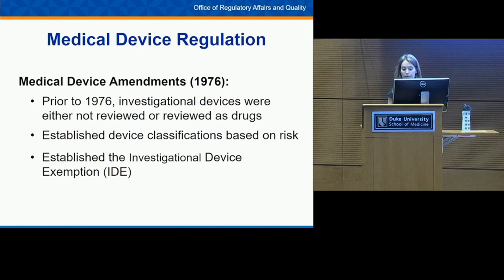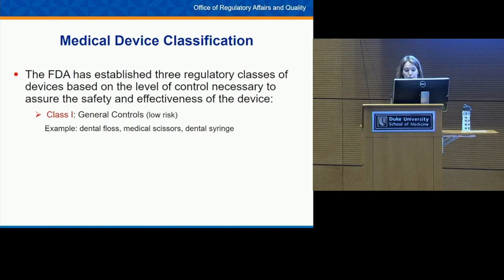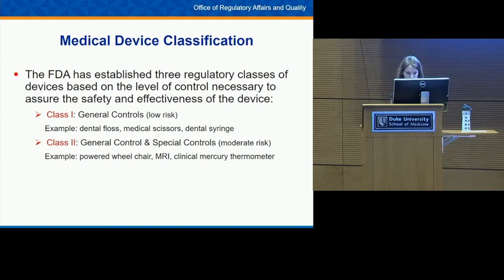With the Medical Device Amendments, FDA established three regulatory classes based on the level of control necessary to assure safety and effectiveness. Class I devices are low-risk — things like a toothbrush, sunglasses, or dental floss — and FDA determined that general controls are sufficient to assure their safety and effectiveness. Class II devices are moderate risk, such as an MRI or powered wheelchair, for which general controls alone are not sufficient, so special controls are also required.